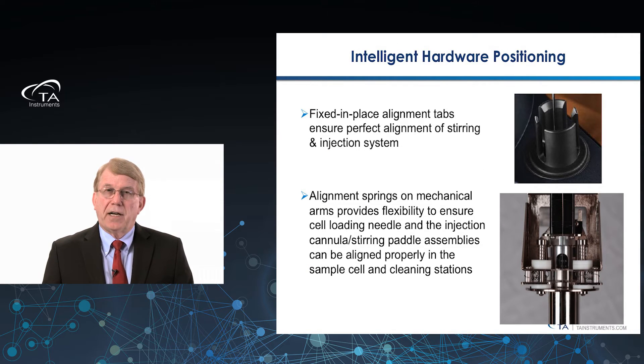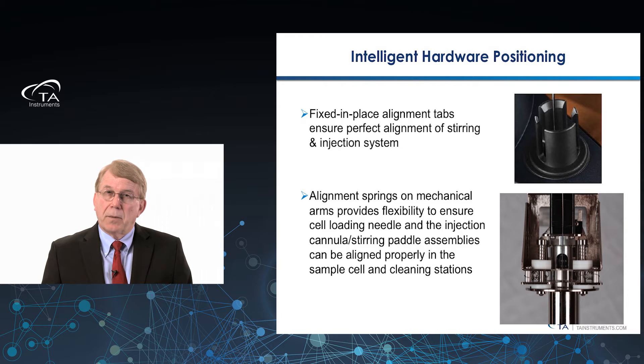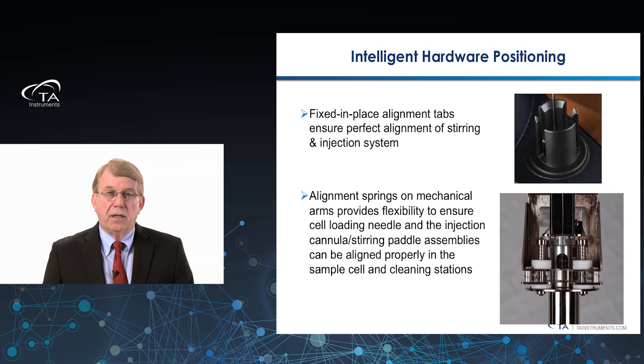Intelligent hardware positioning ensures that as you use an automated system, if it varies a little because of wear or other mechanical factors and is off by just a little, you're not going to damage your instrumentation. Fixed-in-place alignment tabs ensure perfect alignment of the injection system or cell loading system exactly in the cell or washing station. Alignment springs embedded in the mechanical arms allow small adjustments without damaging the hardware. Intelligent hardware positioning ensures the reliability of the mechanical arms as they move time after time under heavy use.